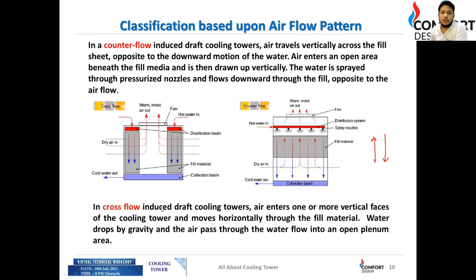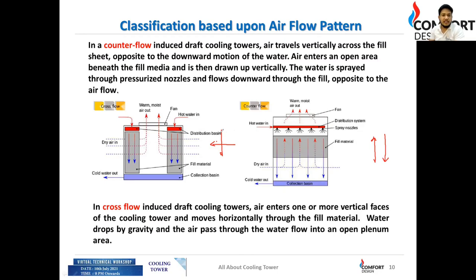In a cross flow induced draft cooling tower, air enters through one or more vertical faces. Hot water comes in from the top through a water distribution basin, while air enters from the side. The air and water flows intersect — they cut across each other rather than opposing each other — which is why it is called cross flow. A detailed study material will be shared.